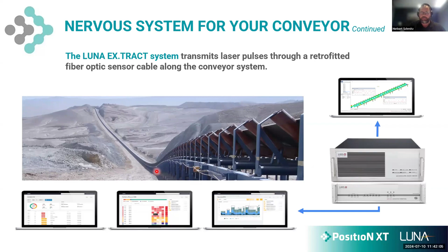Now, depending on applications, we can measure comfortably from -80 to about +500. And in some special applications, we can go -180 to +1000, depending on the sensor cable construction. Being fiber optic, we are immune to vibration, to explosive environments, to radiation. Nothing affects the sensitivity within our system. So it's absolutely inherent. The system for a fire prevention application carries full FM, ULC, VDS, EN certification as well.